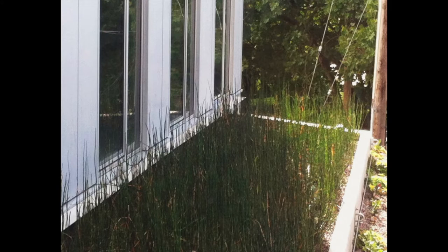Let's take a closer look at this constructed wetland on the third floor. The constructed wetland is a green roof filled with porous gravel and bioretention soils. The plants you see here are horsetails, chosen for their hardiness, their love of water, and their ability to thrive in Seattle's climate. Water is pumped through the system several times through little irrigation drip lines, and as it moves through the system, it's cleaned and most of it is returned back to nature through evapotranspiration — these horsetails return it back to the air.